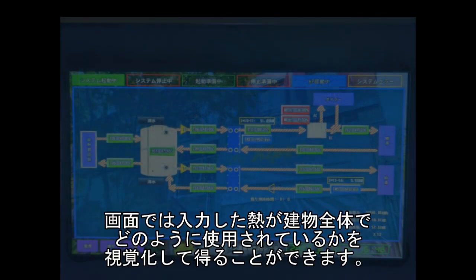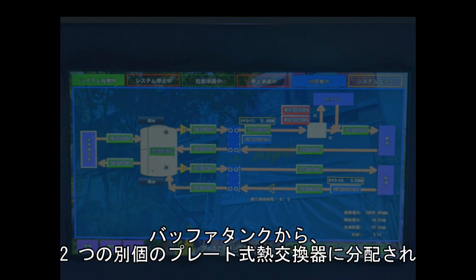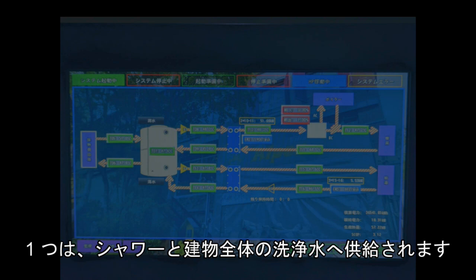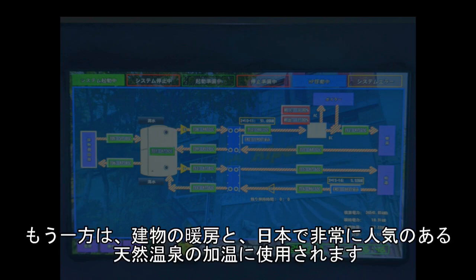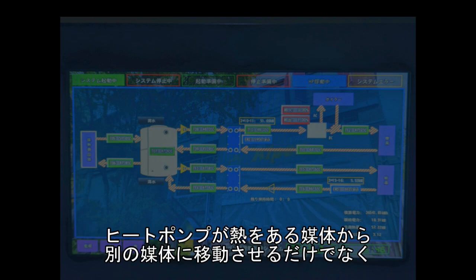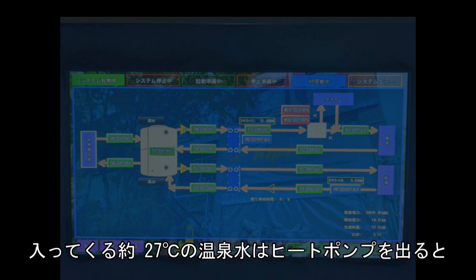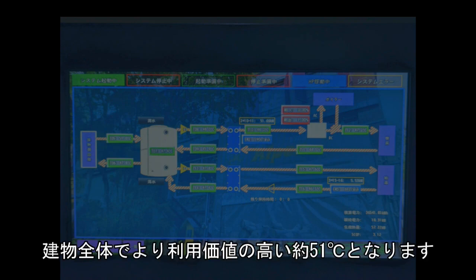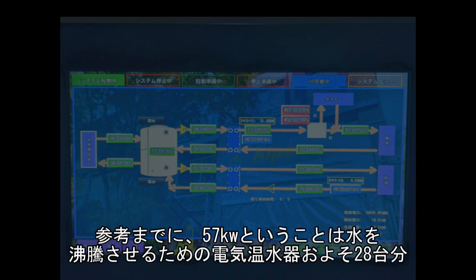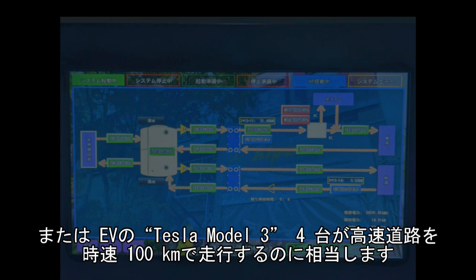In this picture we can get a visualization of how the heat is used throughout the building. From the buffer tank, it distributes to two separate plate heat exchangers. One is used for showering and cleaning water throughout the building. The other is used for heating the building as well as heating the onsen bath or natural spring that's very popular in Japan. Not only does the heat pump move heat from one medium to another, it also raises the temperature. So our onsen water coming in is around 27 degrees. Once it leaves the heat pump, it's about 51 degrees, which is more usable throughout the building. And for reference, 57 kilowatts is roughly 28 kettles for boiling water running at the same time, or 4 Tesla Model 3s traveling at 100 kilometers an hour down the freeway.